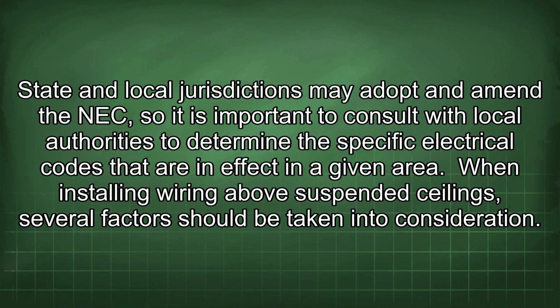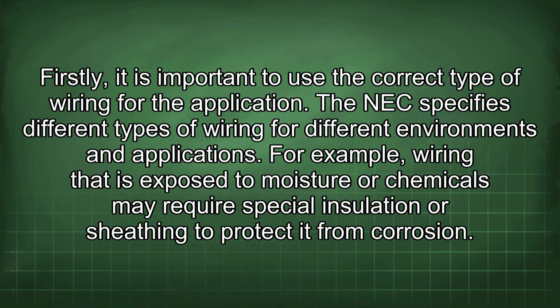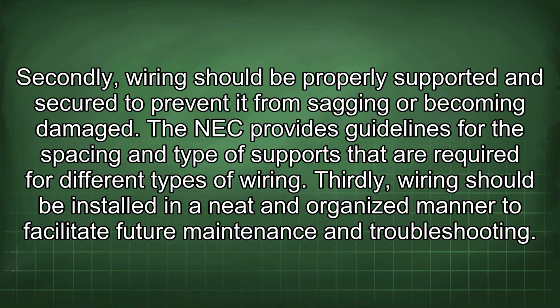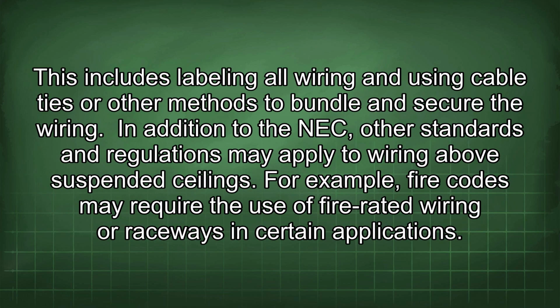When installing wiring above suspended ceilings, several factors should be taken into consideration. Firstly, it is important to use the correct type of wiring for the application. The NEC specifies different types of wiring for different environments and applications. For example, wiring that is exposed to moisture or chemicals may require special insulation or sheathing to protect it from corrosion. Secondly, wiring should be properly supported and secured to prevent it from sagging or becoming damaged. The NEC provides guidelines for the spacing and type of supports that are required for different types of wiring. Thirdly, wiring should be installed in a neat and organized manner to facilitate future maintenance and troubleshooting. This includes labeling all wiring and using cable ties or other methods to bundle and secure the wiring.